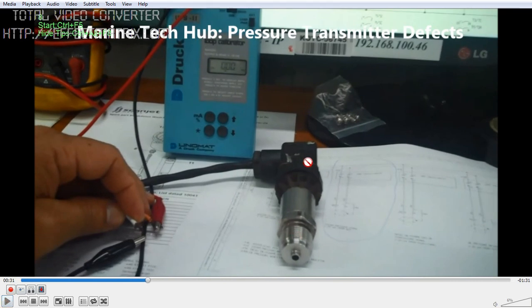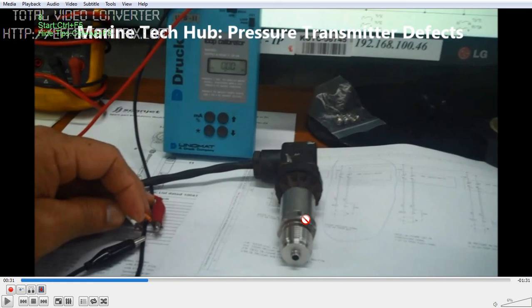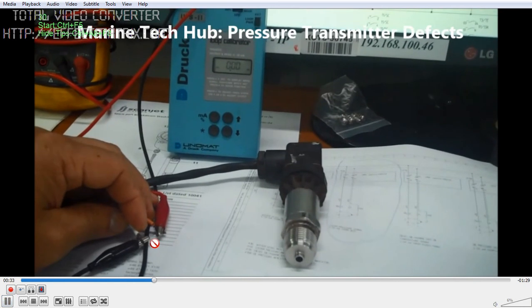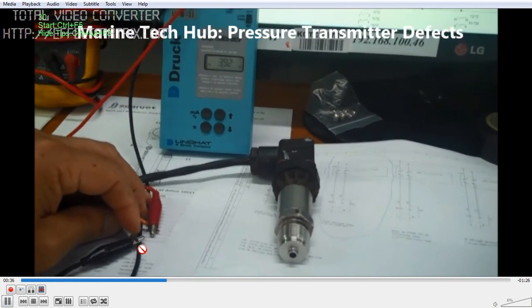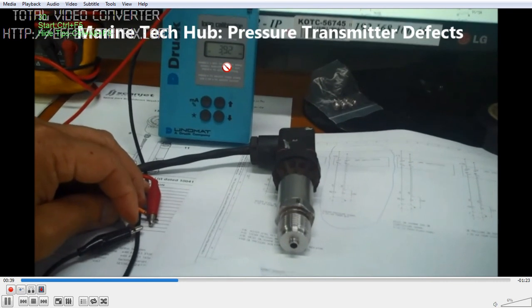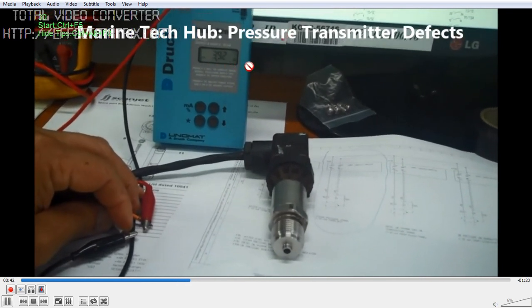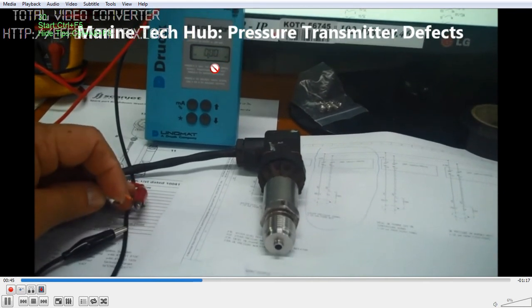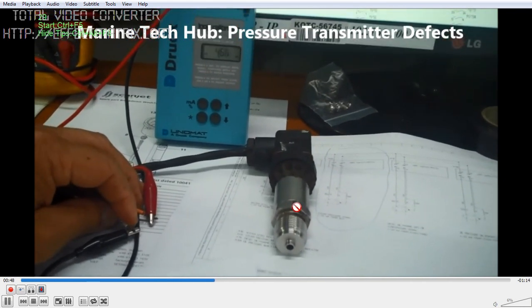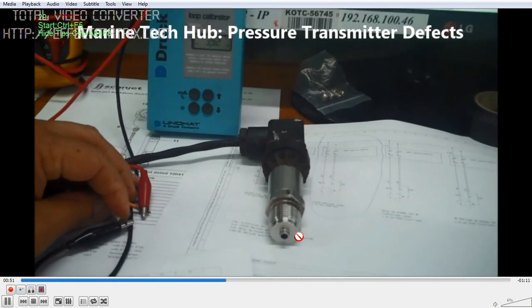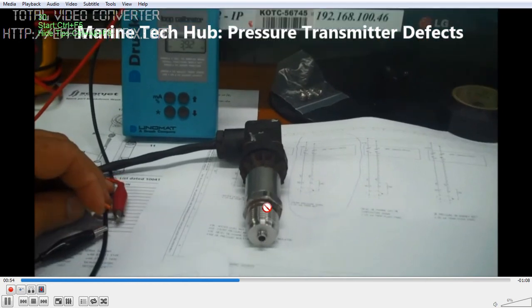I have removed the transmitter. This is the loop calibrator — I have explained previously how to use it. You have the internal and external output here. I will be connecting it to show you whether the transmitter is working. One connection is already on red; I am just touching the other one. You can see it is showing 3.92 milliamps, which is effectively 4 milliamps. If I remove it, the reading goes off. So that means this pressure transmitter is okay.